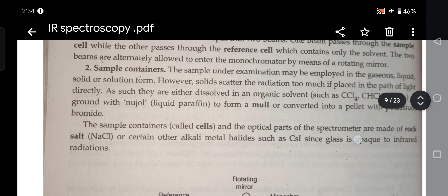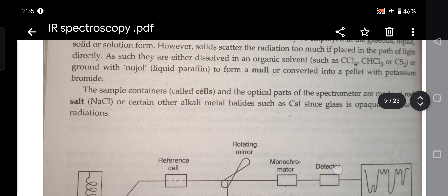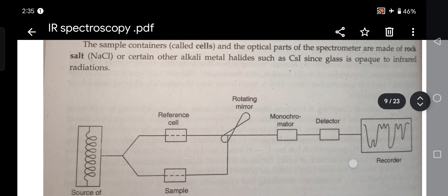However, solids scatter the radiation too much if placed in the path of light directly. As such, they are either dissolved in an organic solvent, or ground with Nujol to form a mull, or converted into a pellet with potassium bromide. The sample containers and the optical parts of the spectrometer are made of rock salt or certain other alkali metal halides such as CsI, since glass is opaque to infrared radiations.